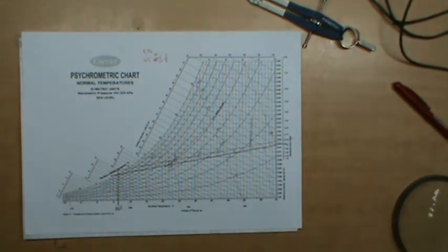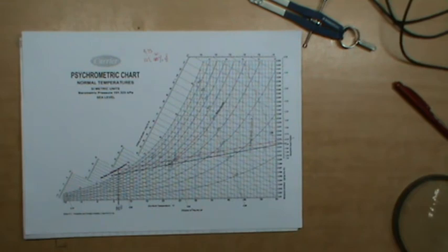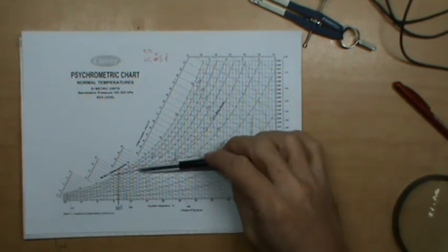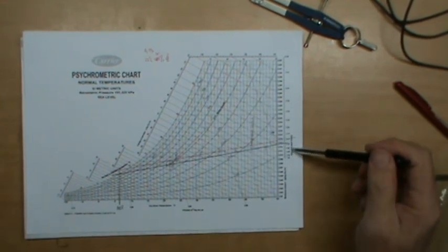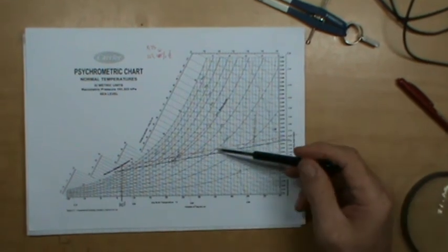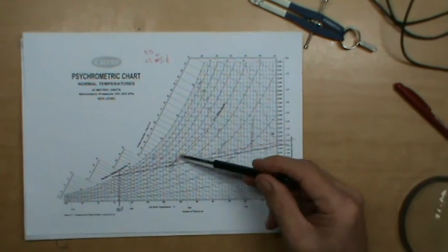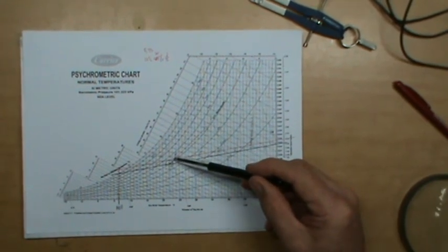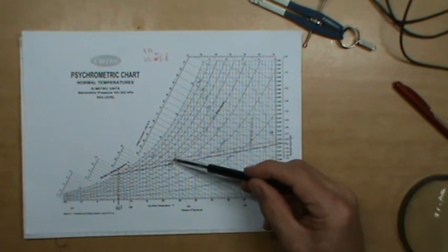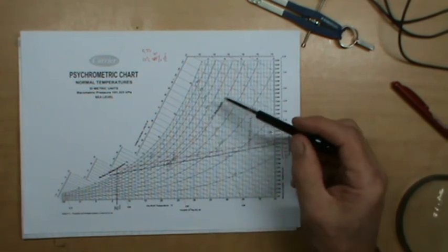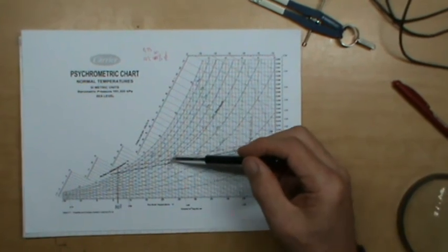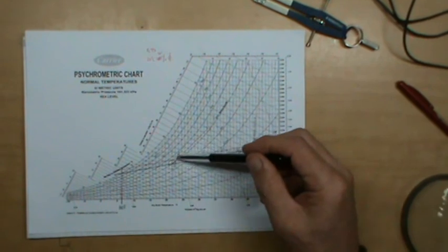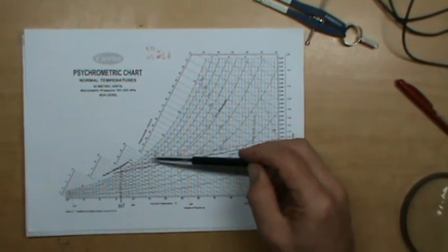When you've got an example that says the internal or the room condition values are 24 degrees and 50% relative humidity, you basically sit back and relax, because you don't have to do the second line, because whatever you've determined in your sensible heat factor on this side over here, you're just going to draw it straight through the 24 degrees and 50% relative humidity, which in the example's case would represent the room condition, but at the same time it also represents the approved comfort position for air conditioning, which is 24 degrees and 50% relative humidity. You just draw it straight through, and you pick up the apparatus dew point over there.